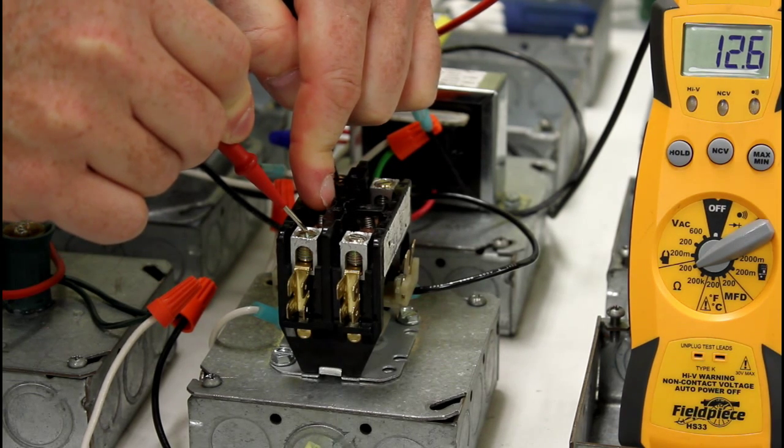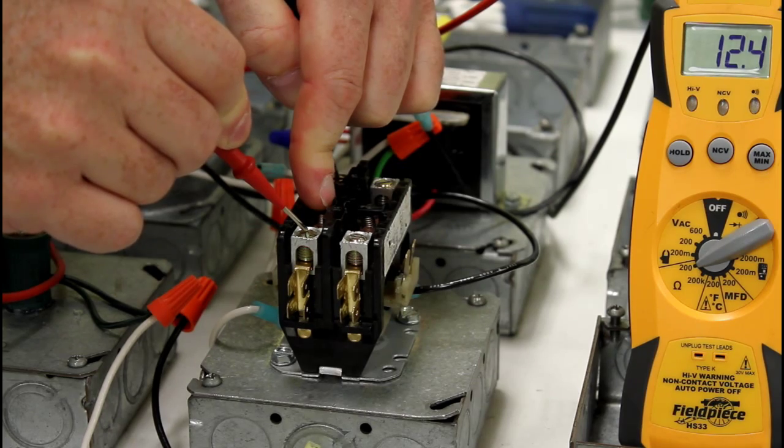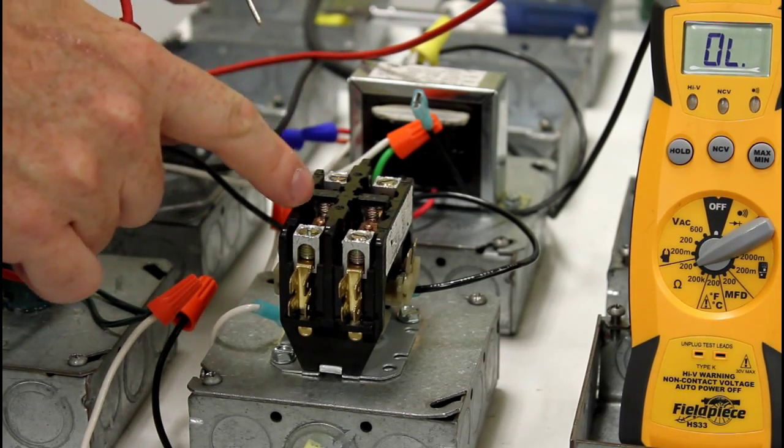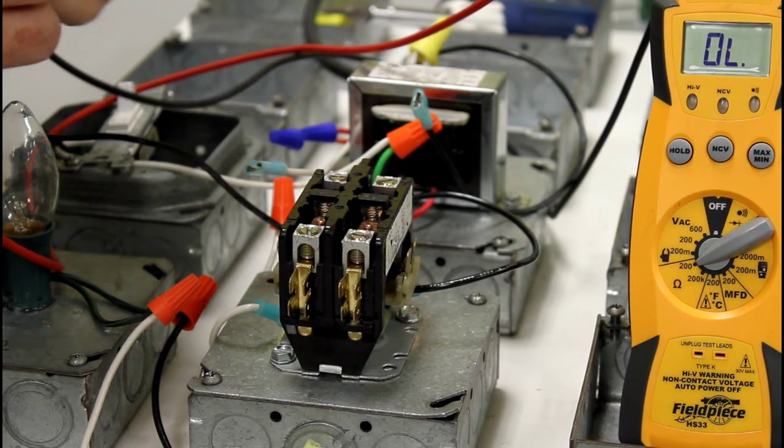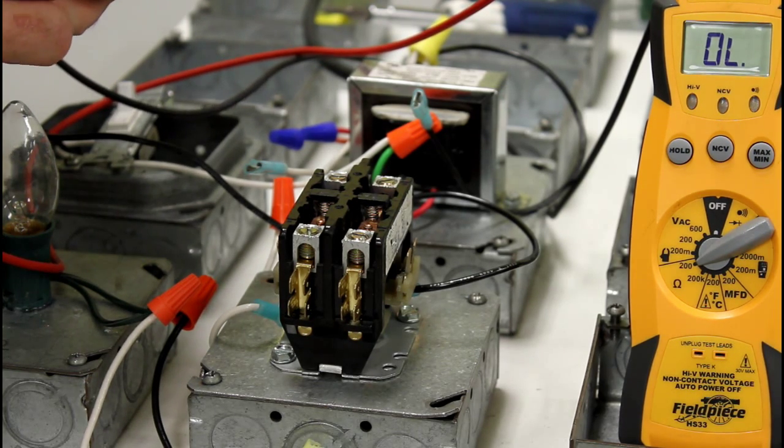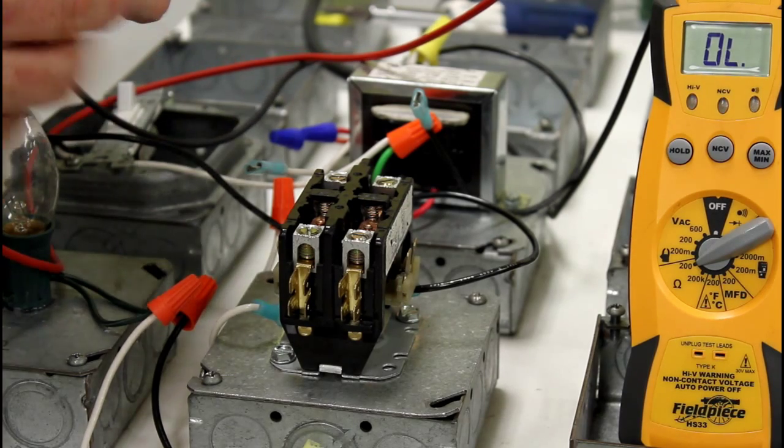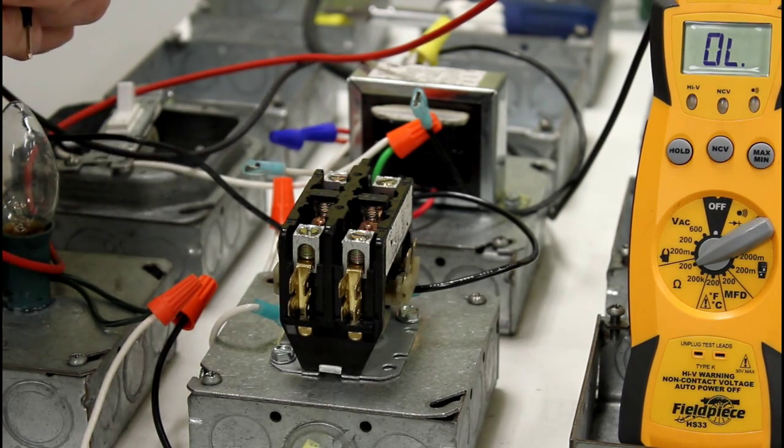I'm going to do the same thing here on contact two. See this one got a little bit more resistance than the last side. So this side's got a little bit more wear and tear than the other side does. Once again, once you start getting more than a couple of ohms, you really should change out the contactor.